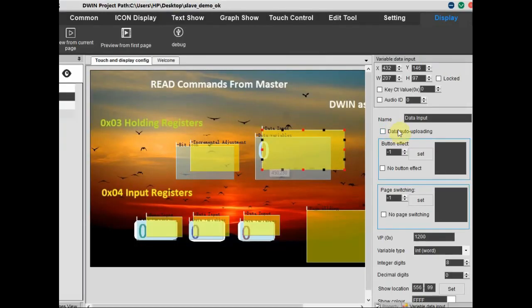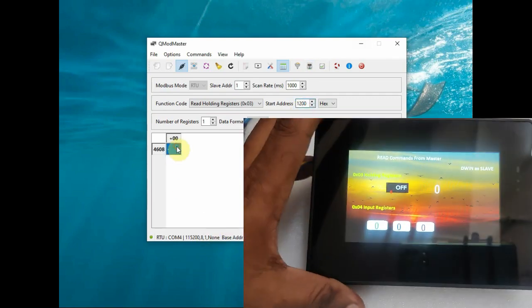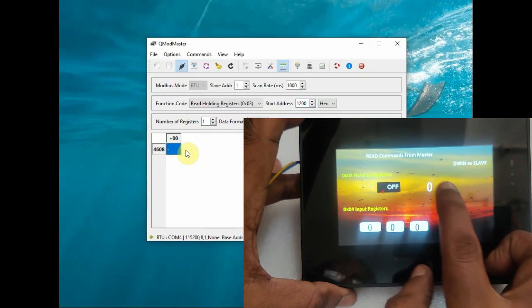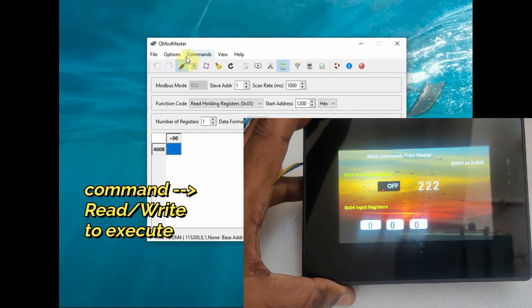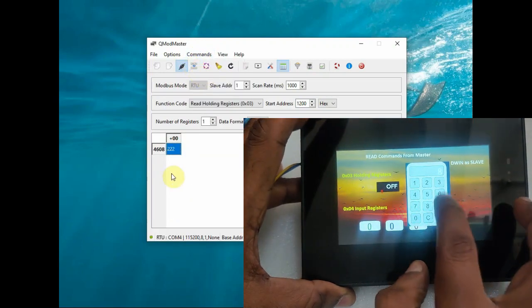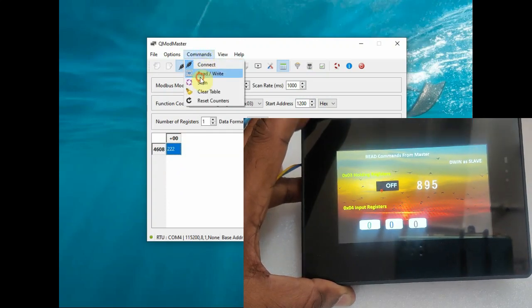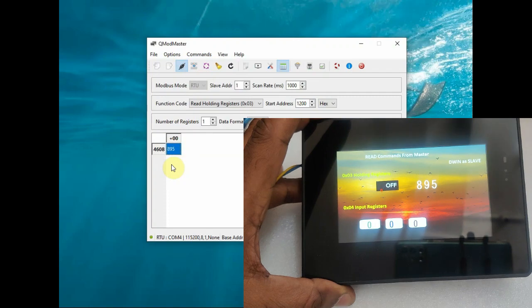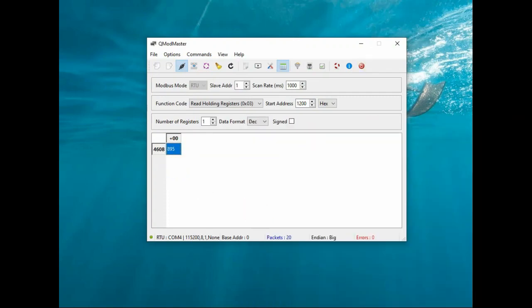The next VP address is 1200 where we used a data variable with keyboard input. Select the start address as VP 1200 and number of registers as 1. Feed the value 222 to the data variable, then click Read/Write on QMod Master - the value will reflect in QMod Master. Change the value and it will reflect in QMod Master. This is data variable input from DWIN slave that is read by the master.